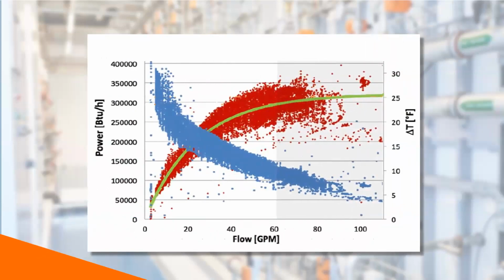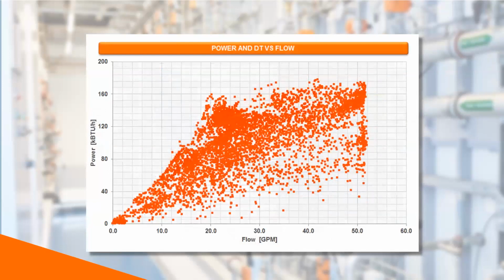So as a follow-up from the previous slide, most coil curves are going to have a much greater thickness. This would be indicative of a coil that's been in place for a little bit longer. That variation in flows, if you look here, that's a lot of BTU, 250,000 BTUs, and there were a lot of various flows that were used to achieve that. This here, although you don't see a traditional curve, there are pockets of dense data which represent delta Ts. And what this shows us is that we can try to stay on the top side of that dotted line and achieve better delta Ts with lower flows.